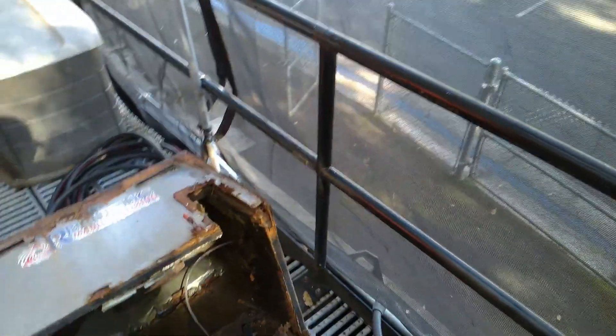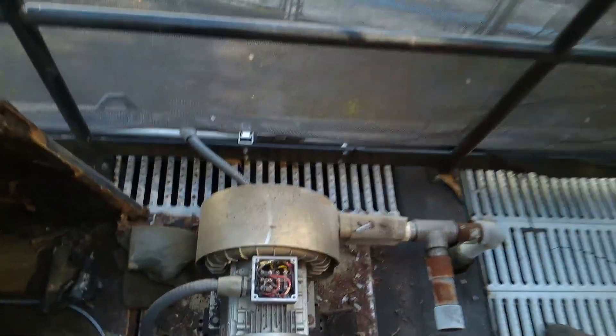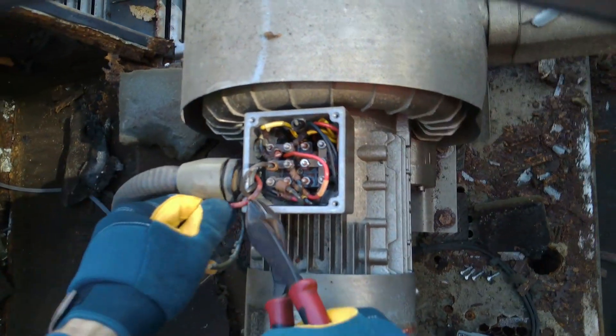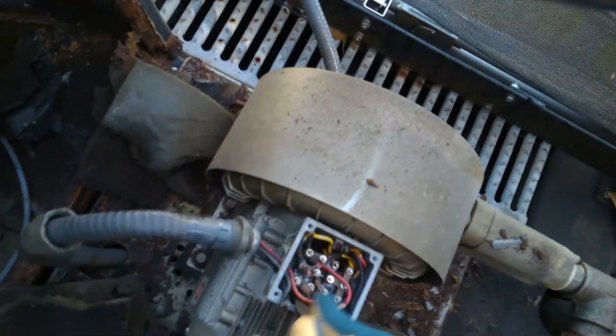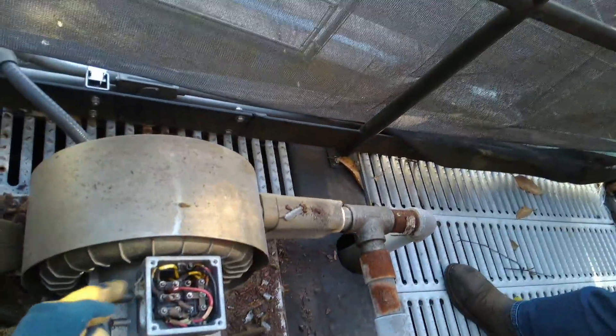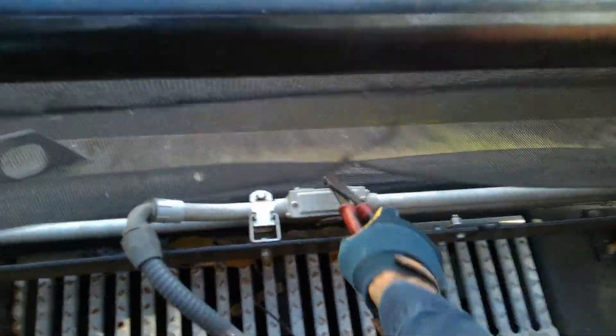Before I go, I'll disconnect that flex and tape it up because this whole thing needs to get replaced. We can shut it off permanently — I'm just going to snip the wires. Look at that — this wire's got to get replaced, everything's gotta go. You can see just by looking at it, it's gone. I think this is aluminum — no wait, that's not aluminum, that was a little plastic plug. The aluminum is okay, didn't quite get that hot. We've got a little junction box right here where we can splice in a new wire and new flex.